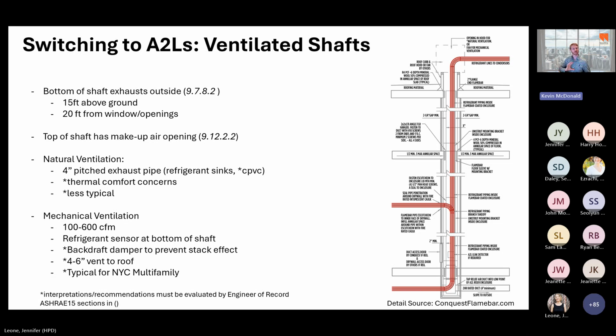There are two different ways that you can approach ventilating these shafts. You can do natural ventilation or mechanical. So you can add a fan or you can do it naturally. If you're doing natural ventilation, that bottom vent needs to be pitched down. And basically this is kind of impossible in a multifamily building unless you're on the second floor or above, because you're not going to be more than 15 feet off the ground. So ostensibly we're looking at mechanical ventilation for most of the projects that you will be working on.